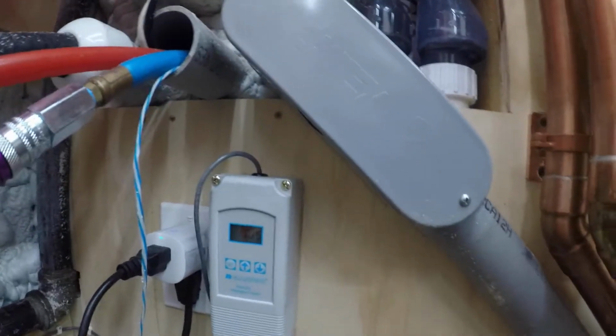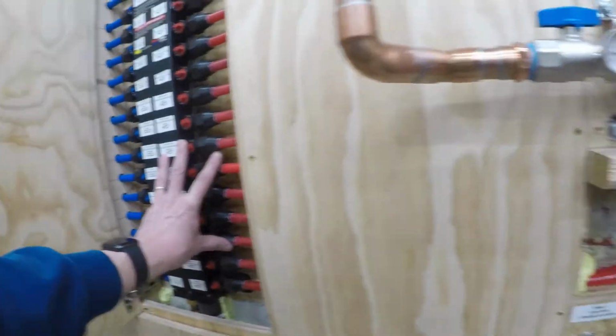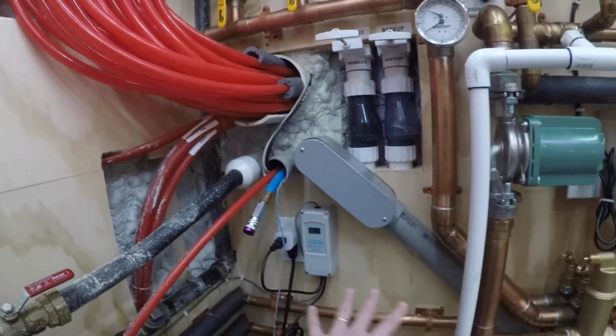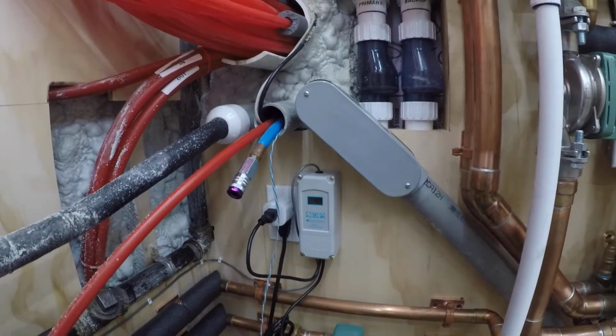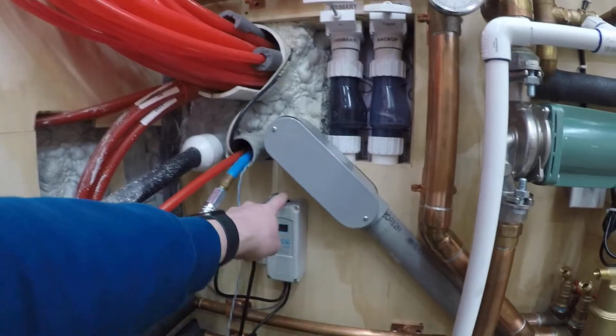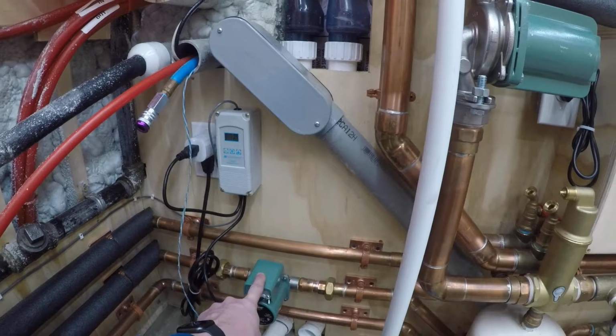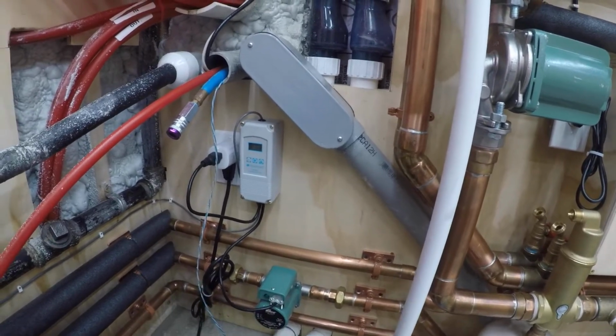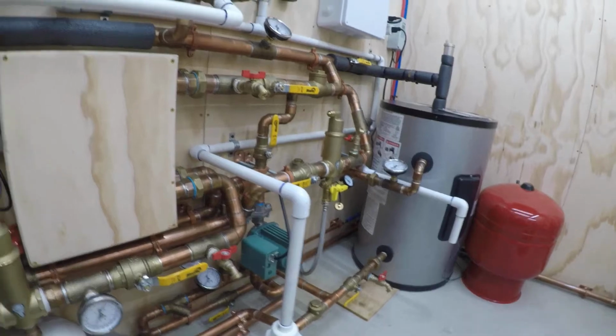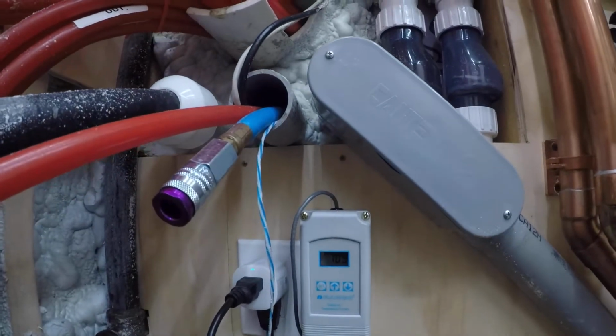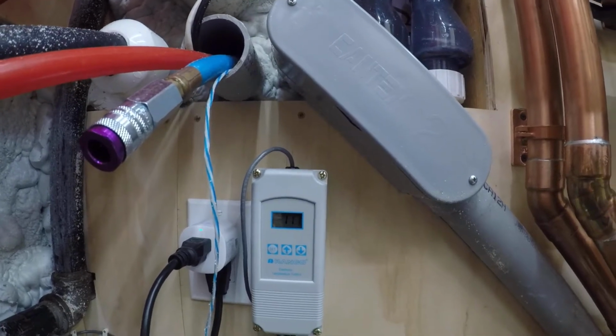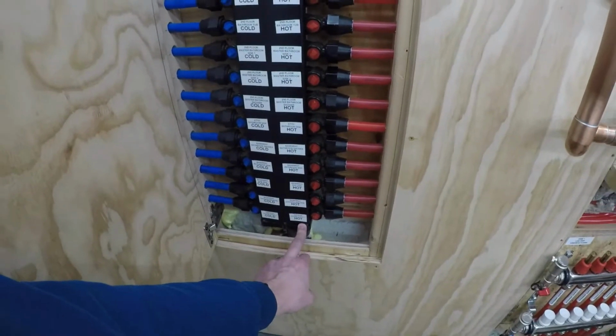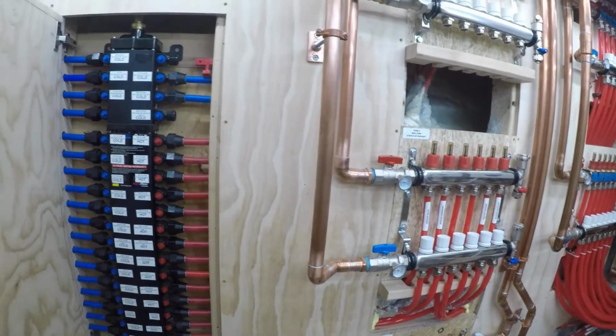It just sensed that that water is 105 degrees. Okay, and the sensor is right here. Tried to get it as close to this as I could. So as the hot water in that line cools down to 105, and this aquastat senses that, it turns on this pump. So right now, this pump is sucking hot water from the tank up through here and pushing it back on the recirc line into that neutral zone right there. Okay, and as you'll see, it's already back up to 109, 110, 111, 112. So that keeps the hot water pretty much right here all the time. So when we turn on a fixture, you've got hot water pretty quick.